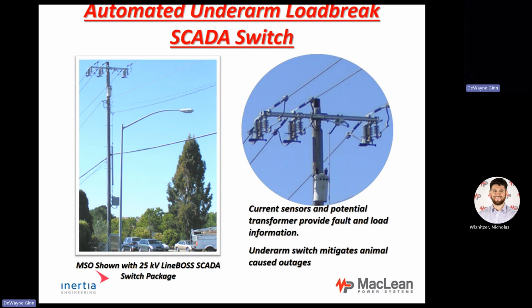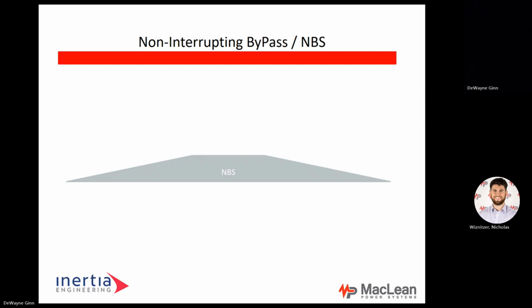It can become an automatic sectionalizer and open and close that switch without having to have somebody at the switch to open and close it. In other words, if I lost, say, current, it could have a time delay and open up that circuit. And when the voltage comes back on, it senses it. It could be a time delay and closes in when it needs to. Or it could be operated by the control house.